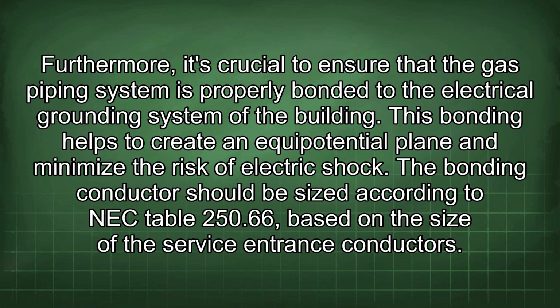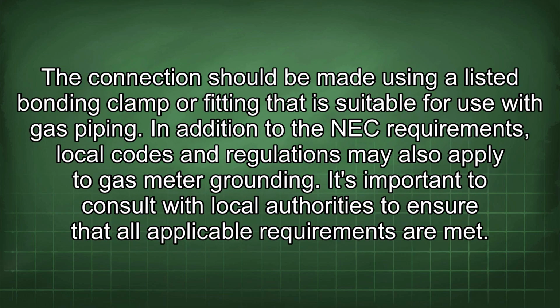Furthermore, it is crucial to ensure that the gas piping system is properly bonded to the electrical grounding system of the building. This bonding helps to create an equipotential plane and minimize the risk of electric shock. The bonding conductor should be sized according to NEC Table 250.66, based on the size of the service entrance conductors. The connection should be made using a listed bonding clamp or fitting that is suitable for use with gas piping. In addition to the NEC requirements, local codes and regulations may also apply to gas meter grounding. It's important to consult with local authorities to ensure that all applicable requirements are met.